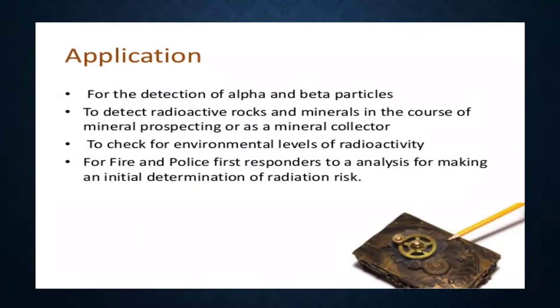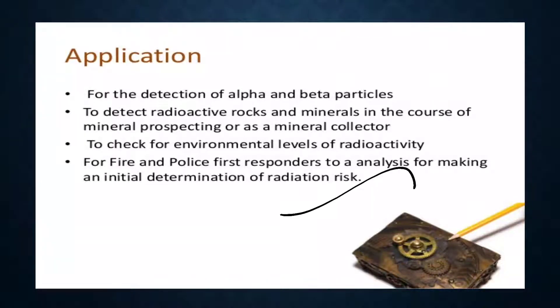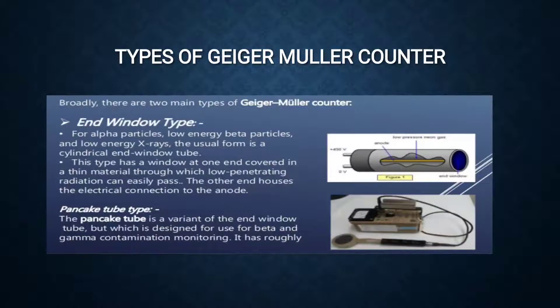The applications of the GM counter include detection of alpha and beta particles, detecting radioactive rocks and minerals during mineral prospecting, checking environmental levels of radioactivity, and use by fire and police first responders to make an initial determination of radiation risk.